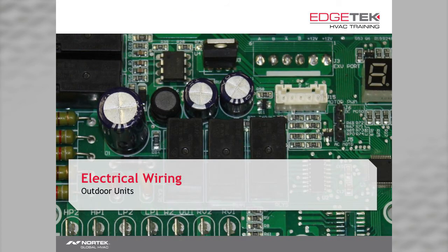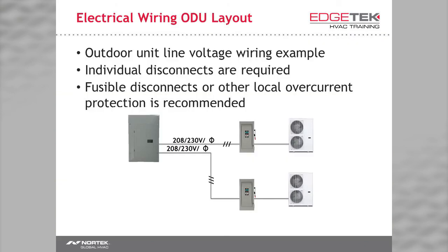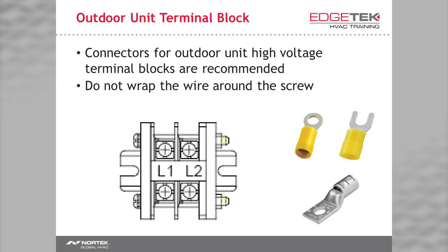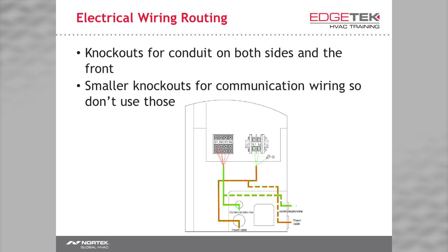Now let's talk about wiring in the outdoor units. Our mini VRF outdoor units are also all 208-230 volt single phase. You'll need a properly rated disconnect for each outdoor unit. I again suggest using an appropriate electrical connector at your terminal block for a solid connection. You can route your wiring out of the front or side via standard knockouts.